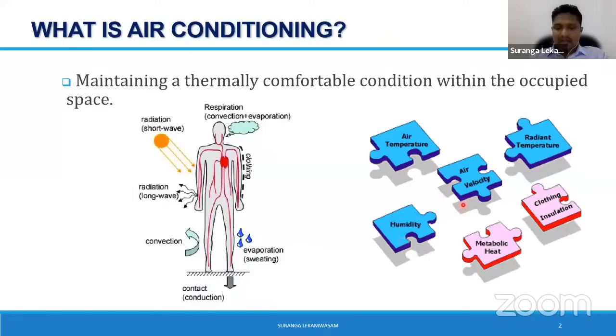Then equally important, air velocity, because when the air velocity interacting with your body is high, your rate of heat removal is also high. Therefore, you can play a lot with this air velocity parameter. In modern society, modern industry, we are so keen on energy aspects. There is a concept called hybrid cooling. It's like this, for example, you are running your air conditioner at 24 degrees, right? So you feel a certain level of comfort. Now, let's say you run your air conditioner at an elevated temperature, say 27 or 28 degrees, and you switch on your ceiling fans, if you have installed ceiling fans.